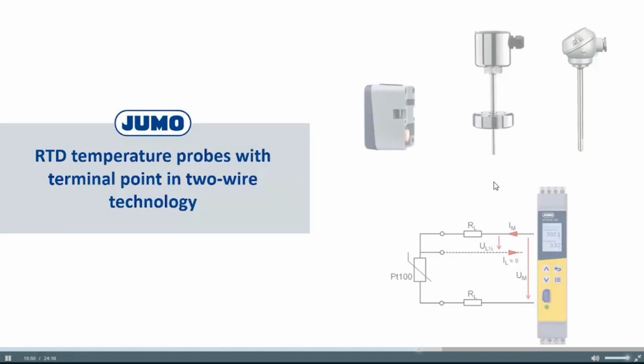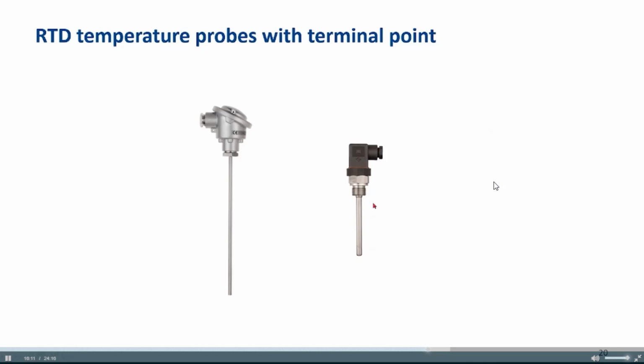Okay, let's look at RTD temperature probes. In 2-wire technology, we said this is a little bit problematic because of the offset. But if they have a terminal point, then it's not such a big problem. I'll show you. So I'm talking about these sensors here. As a customer, I need to give my own cable to the sensors. So they have a terminal point here in this head, or I make my terminal point here in this connector. And let's look at what the situation is if we have these probes in 2-wire technology.